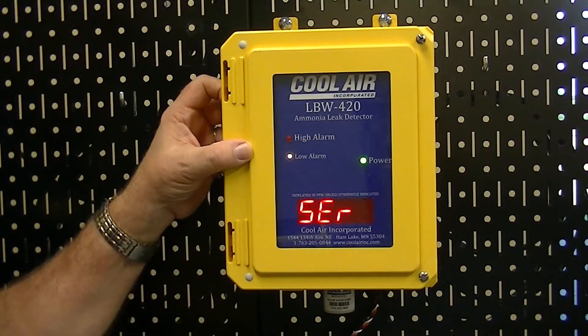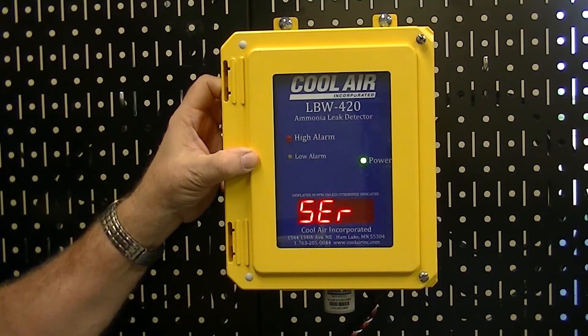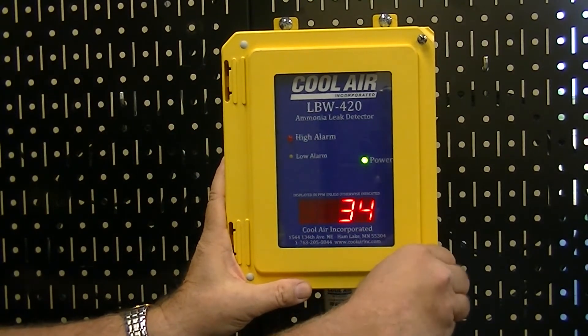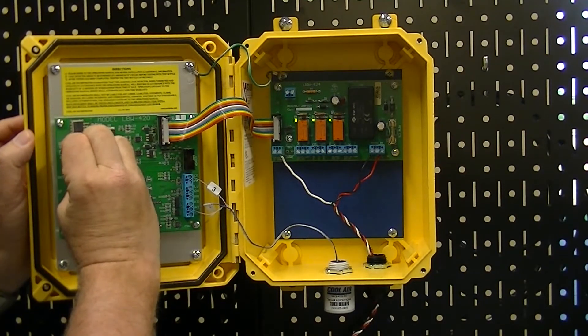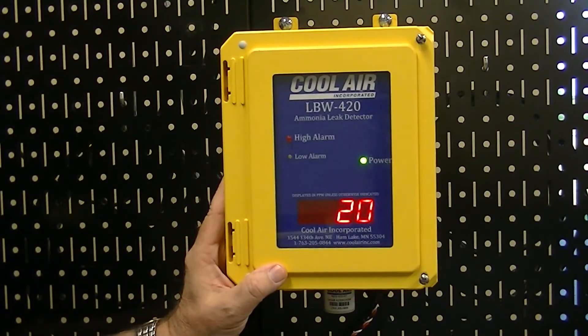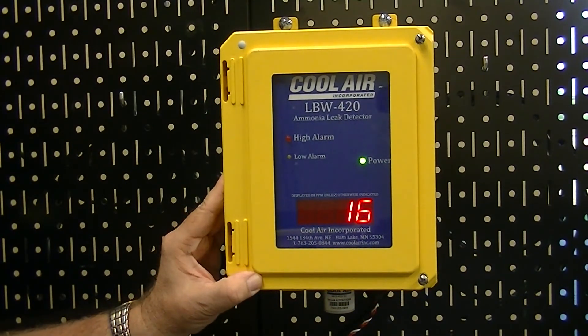Once the detector is reading below the low alarm set point you can move the service mode jumper back to the off position. This completes the calibration of the LBW 420 with the electrochemical sensor.